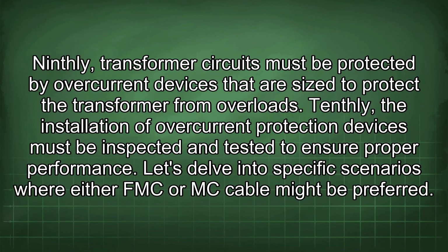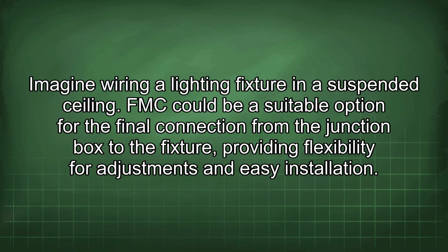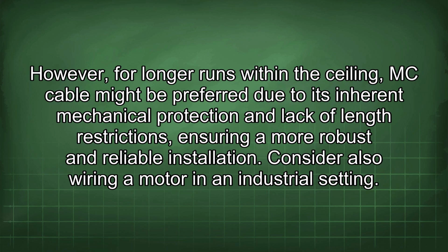Let's delve into specific scenarios where either FMC or MC cable might be preferred. Imagine wiring a lighting fixture in a suspended ceiling. FMC could be a suitable option for the final connection from the junction box to the fixture, providing flexibility for adjustments and easy installation. However, for longer runs within the ceiling, MC cable might be preferred due to its inherent mechanical protection and lack of length restrictions, ensuring a more robust and reliable installation.